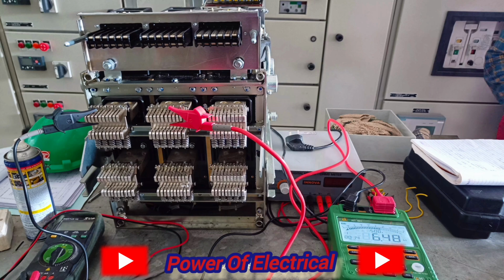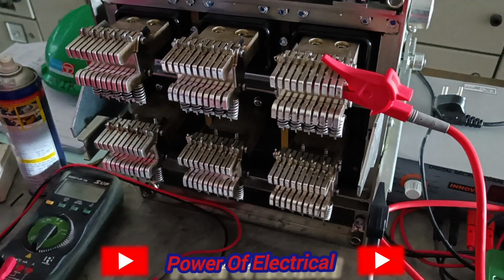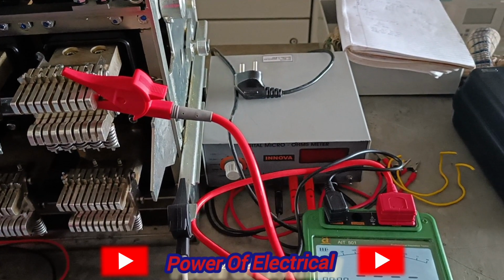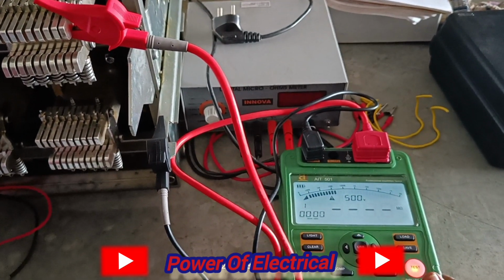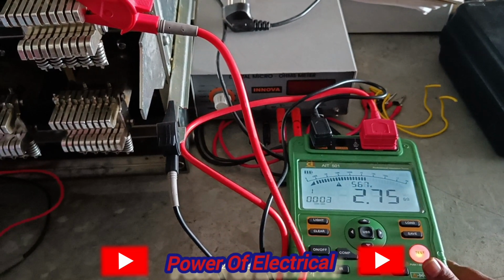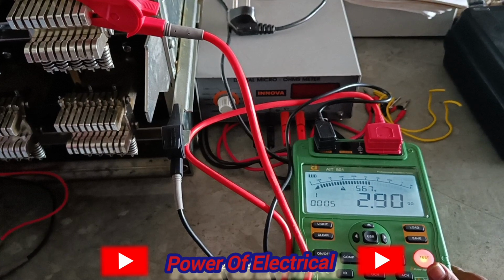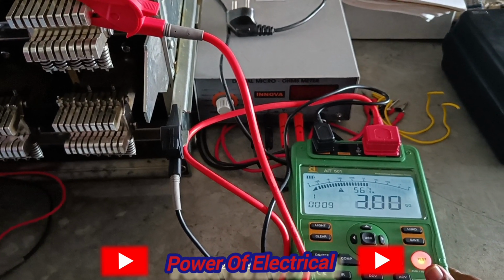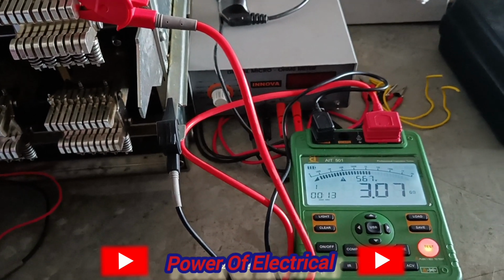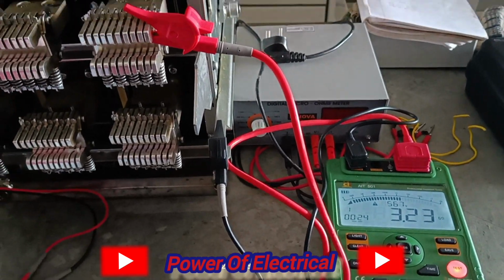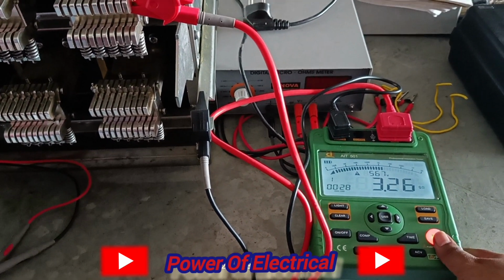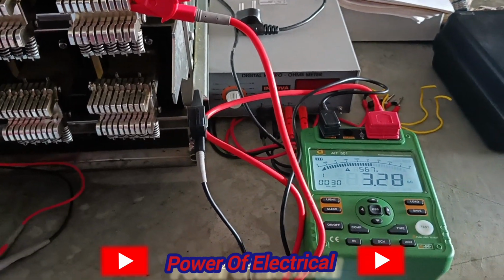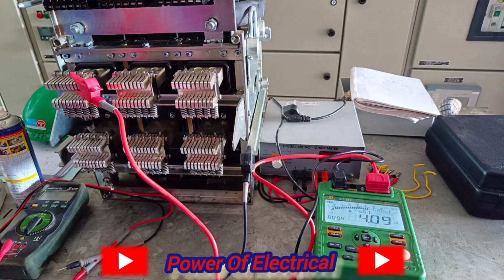Now we are going to the IR testing of phase to earth, meaning R to earth, Y to earth and B to earth. After connecting the probe between phase and earth, we apply the voltage of 500 volt and we get the IR value. The same process is followed for the remaining two phase to earth sequences.